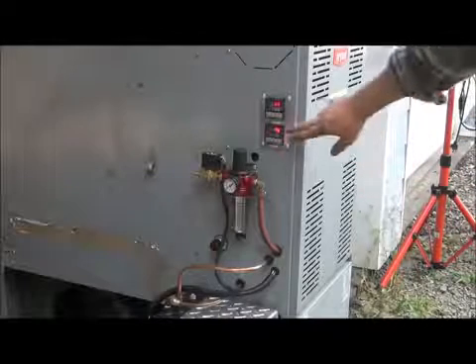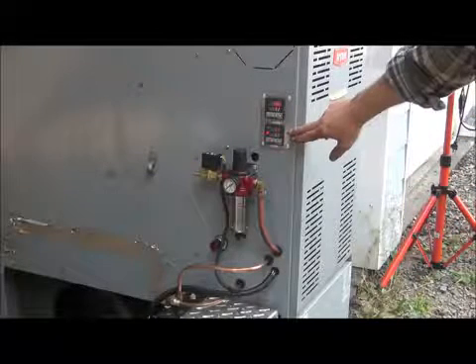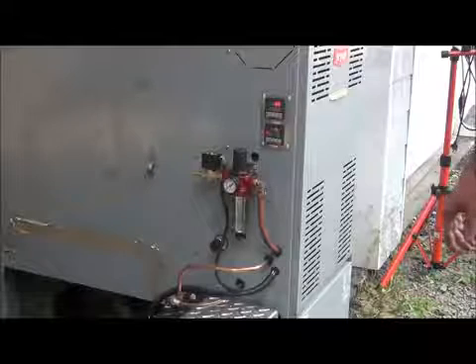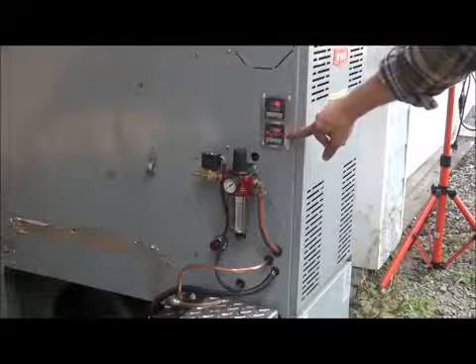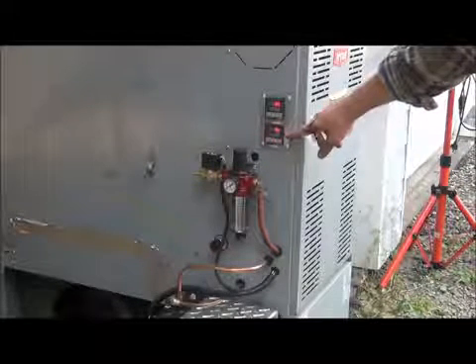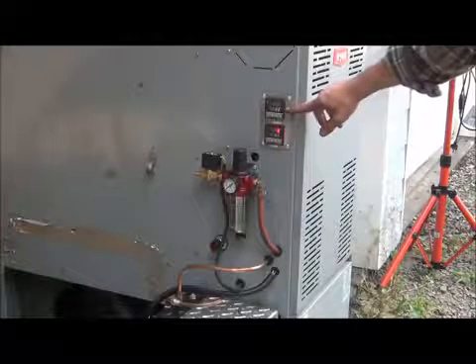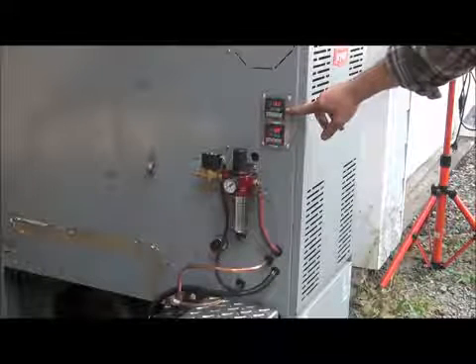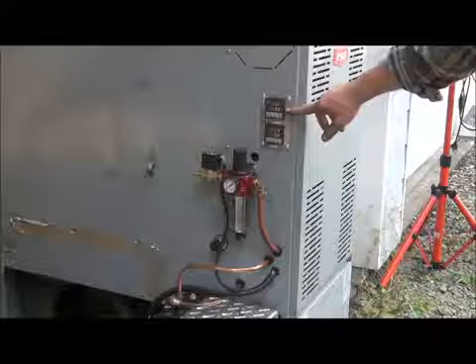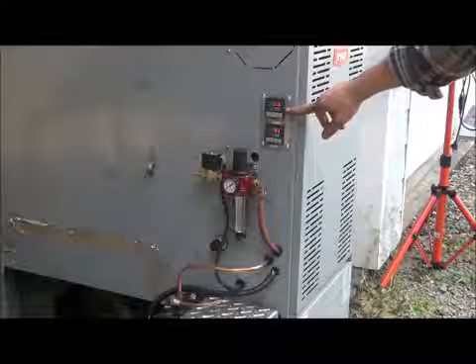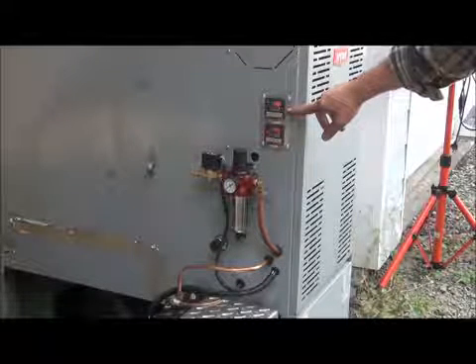And what will happen is once these get up to their pre-programmed set points, then it will allow the burner to light off. So as you can see, the nozzle temperature is getting right up there. We're almost at our set point right now. The temperature of the oil in the tank moves a little bit more slowly because it actually has to heat up all the oil that's in the tank. So it'll take about 1 to 2 minutes before that oil is up to temperature.